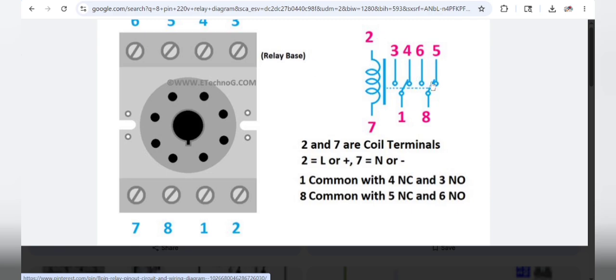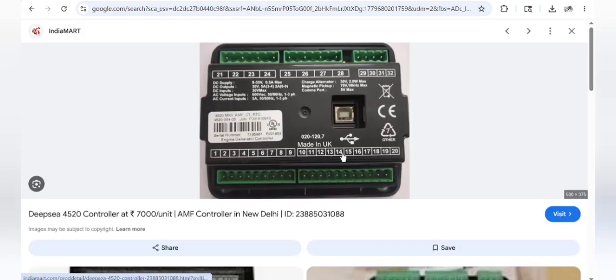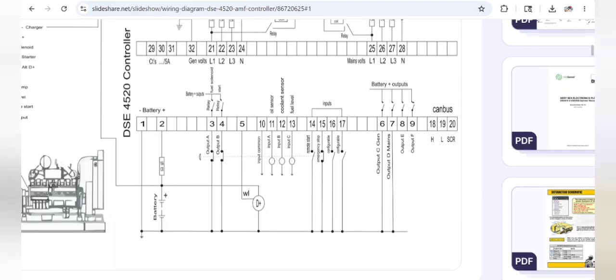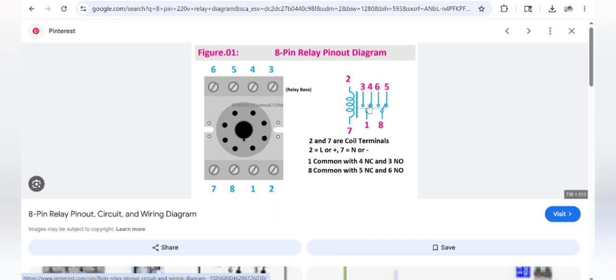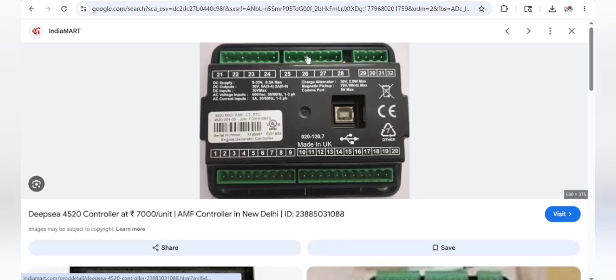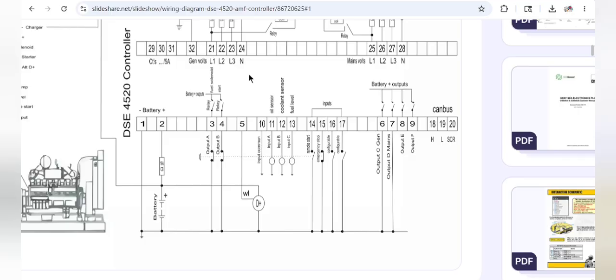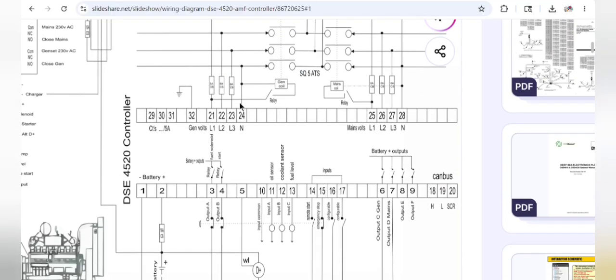What will happen now? When the main power is available, these two contacts will break, going to the normally open position, and your 12 volt or 24 volt negative will not be fed to pin 14. When your main power is available, your relay is also energized, and this contact will be broken in this position. When your main power fails, this contact goes to the normally closed position, and this will start feeding to pin 14. When the controller senses the ground signal on pin 14, it will start the generator automatically, shift the generator load to your load, and close the genset contactor.